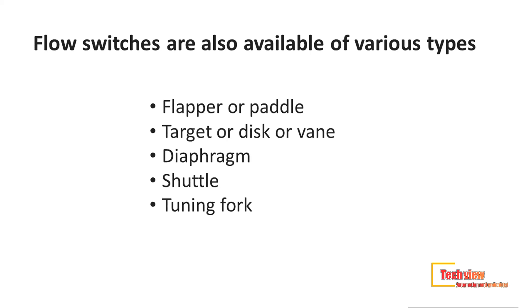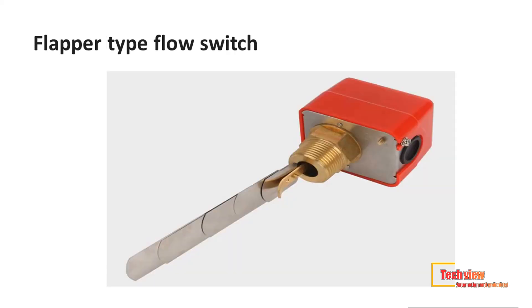Types of flow switches: flow switches are available in various types such as flapper, target or disk, diaphragm, shuttle, piston, tuning fork, etc. The flow switch consists of a flapper device hanging with the flat surface facing the direction of flow through a hinge. A permanent magnet is connected to this end.